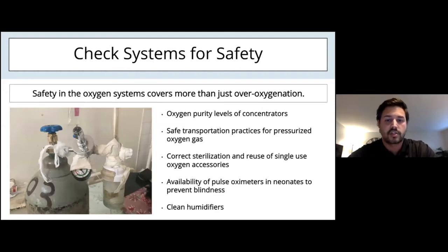And safety in the oxygen system covers more than just over-oxygenation, okay? It covers oxygen purity levels in concentrators. It means understanding safe transportation practices for pressurized oxygen cylinders. So, when you look at the cylinder, there's a valve on top, and these cylinders are very high pressure. And if it falls over during transportation and that valve gets damaged, that cylinder essentially becomes a high-speed bullet moving through your hallways and your wards, and can very much hurt people. So safety, huge. When you're transporting cylinders, have a safety cap on that one.